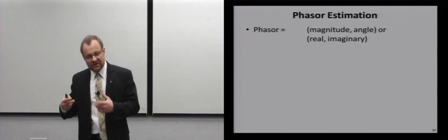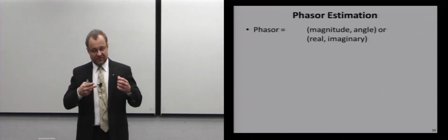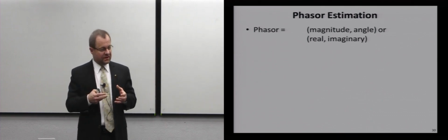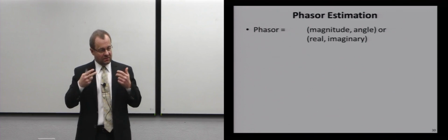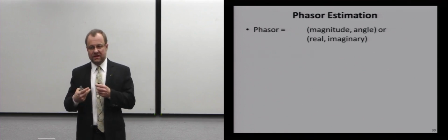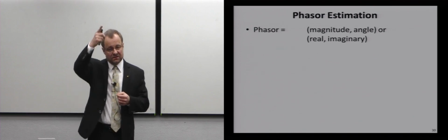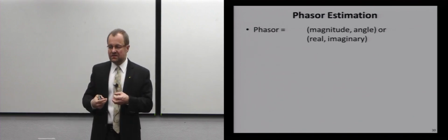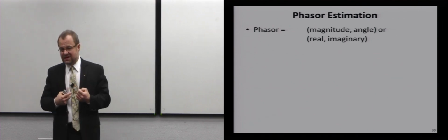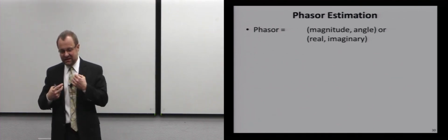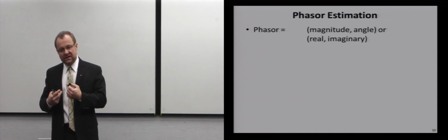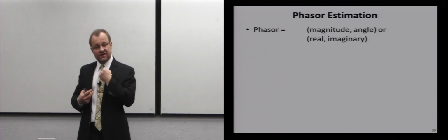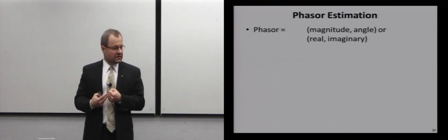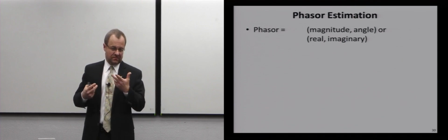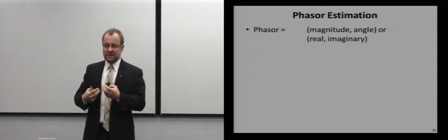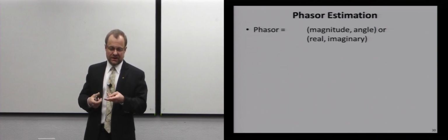For somebody who builds a device, the challenge is different: the thing changes on me. It has different things in it than just the sine wave. It has harmonics. It's distorted because maybe I have CT saturation, or it has this decaying DC offset. I am rushing to make a decision, and I want to estimate the real and imaginary part as fast as I can, and as accurately as I can. Because if I overestimate it, I will trip when I shouldn't. If I underestimate it, like a current magnitude, I will trip late or not at all when I should, right?